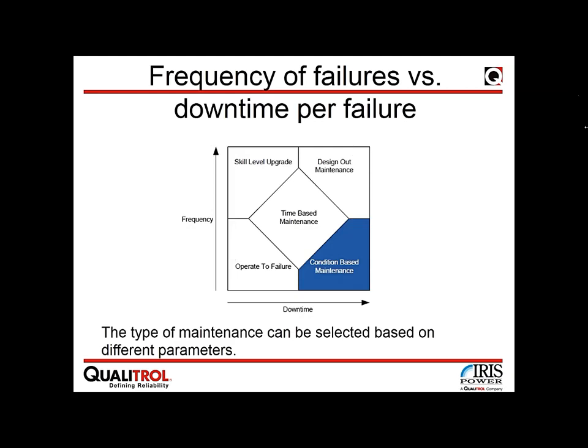A chart shows appropriate monitoring type based on downtime versus frequency. Problems that happen frequently but take little time to fix relate more to operator skills rather than condition-based maintenance. The opposite corner — problems that happen rarely but cause significant downtime — is where condition-based maintenance is most useful in minimizing that large expense.